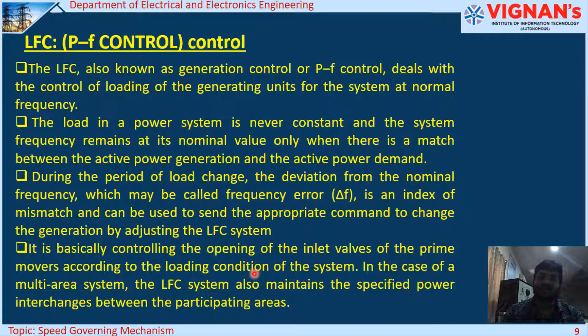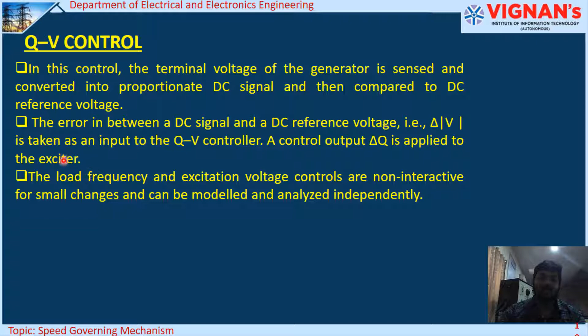Now, QV control is not a separate entity. It comes along with the PF control, but it is an independent loop because of the mismatch in the time constants of the PF control and the QV control. QV control occurs almost instantaneously, so it can be considered independent of PF control. In this control, the terminal voltage is sensed and an appropriate DC signal is given to the field excitation, thereby correcting the voltage mismatch. Any mismatch in the reactive power at the load will lead to a change in voltage, so the reactive power has to be compensated such that changes in the voltage are taken care of by the exciter.